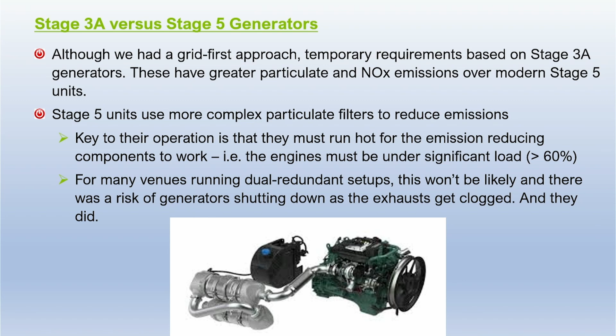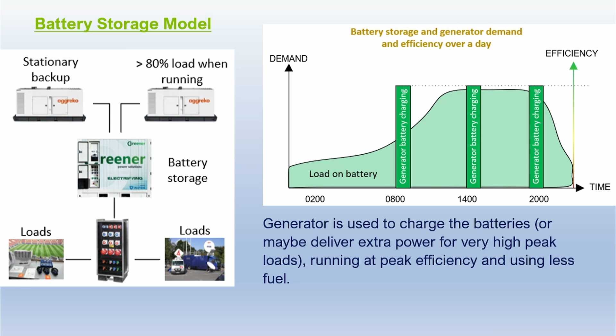So that automatically led to the concept of deploying batteries. As I said, it was much more of an exercise in PR in terms of getting people on board and making sure they're happy with the technology. We did have some teething troubles, as we'll show you in a sec. But the basic principle is, for the most part, you run the loads on the battery, and then you just use the generators to charge up the battery. When you're actually on air or live at the time, you can run the generators as a parallel backup as well, just in case the batteries fail. We had a lot of success with that.